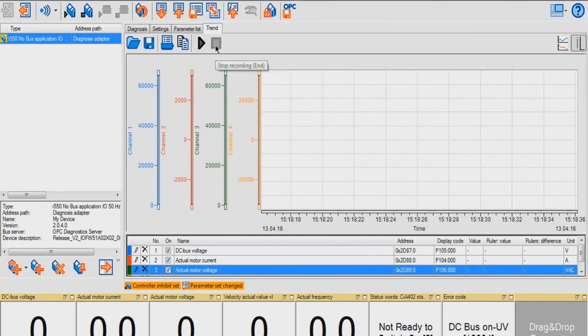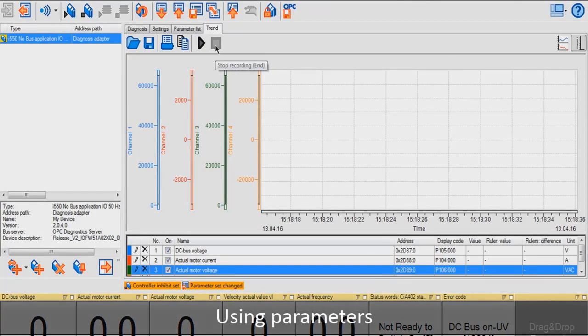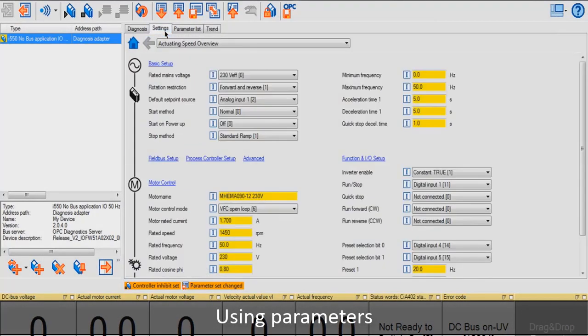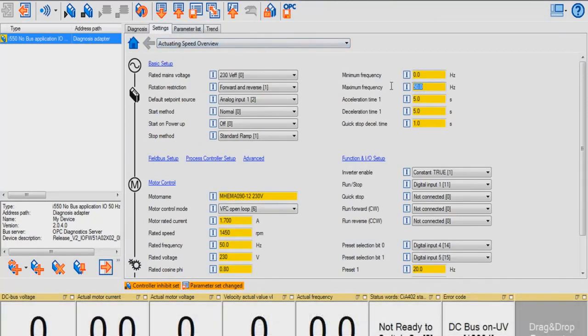Now, we're going to be talking about how to use some of the parameters. We're going to go in the Settings page and change the maximum frequency to 60 Hz, as well as Acceleration and Deceleration Time to 3 seconds.